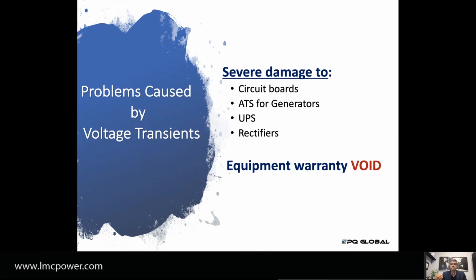What happens is the generator could be in great condition, but if some kind of transient comes into the building from the outside, the very first thing affected is the automatic transfer switch that has electronics, there in case of an emergency to transfer power to a generator. Under these emergency conditions is when you realize that the automatic transfer switch will either not transfer, because it sees a certain level of transient, or if the transient is higher, it actually burns down.